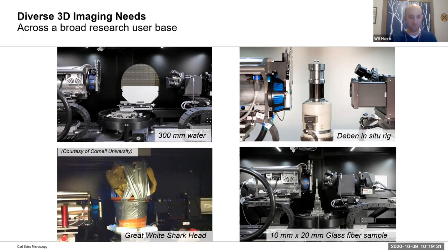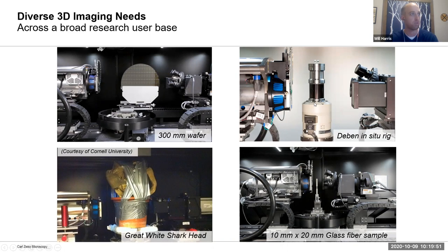Mounting for x-ray imaging is not like SEM or TEM where you need to be very careful about coating your sample or mounting it properly in a vacuum environment. For x-rays it's quite a bit simpler — you just have to make sure it's not going to move. You can also incorporate a variety of in situ rigs.